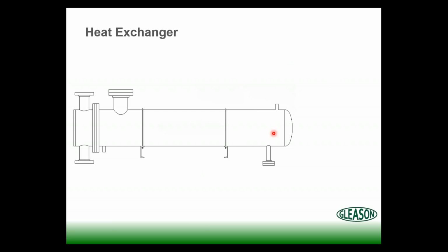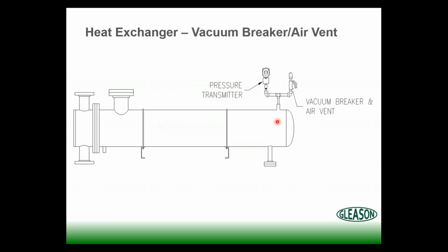This connection here, we walk through plants all the time and we see everything there except what it's designed for. I see a plug in it from the factory. I see a pressure gauge. I see a transmitter, all these different things. But what it's designed for is a vacuum breaker. A vacuum breaker simply senses that negative pressure, takes the thumb off the straw, so to speak, and lets the condensate drain out through the steam trap as it's designed to do.